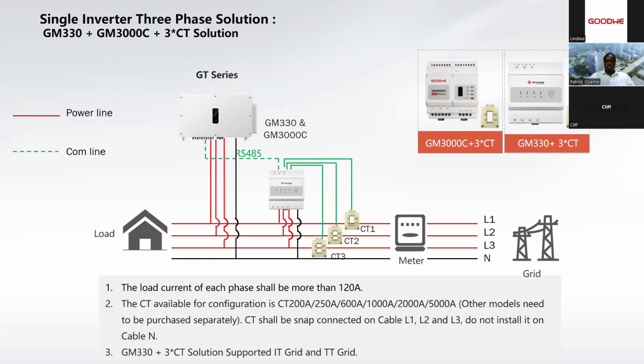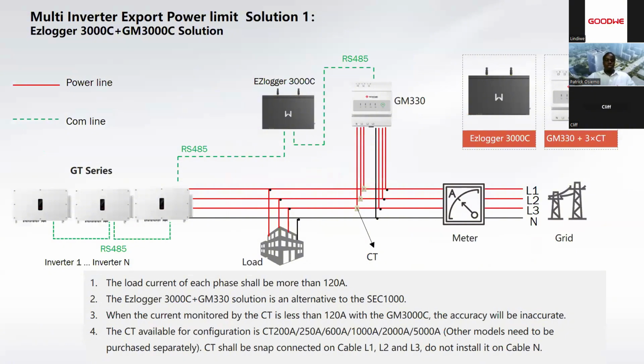from the inverters. Now, the next solution is when you want to include a number of GT series inverters along with the EasyLogger 3000C. The EasyLogger 3000C will be communicating with the GM 330 smart meter to know your load consumption, as well as give the system a target generation. Similarly, we employ the same scenario with the GM 330 and third-party CTs. The smart meter communicates with the EasyLogger 3000C via the RS-485 cable. And if you utilize the EasyLogger 3000C, you'll be able to connect a number of inverters, particularly a number of GT series.